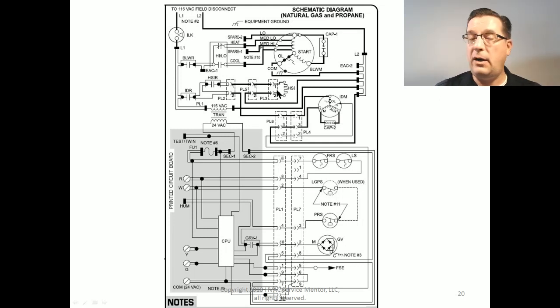So in this case, if our hot surface igniter doesn't glow, is it possible that something in this circuit has physically broken or fails to operate even though it's supposed to? Absolutely. That would mean a bad control board. We have to replace the whole thing. So we want to look to see, what is the job of this control board to do? It's actually to close these relay contacts, and that's it. It doesn't know if the igniter is connected. It doesn't know if it's glowing. It doesn't know any of those things. All it knows is that it's supposed to close these contacts.